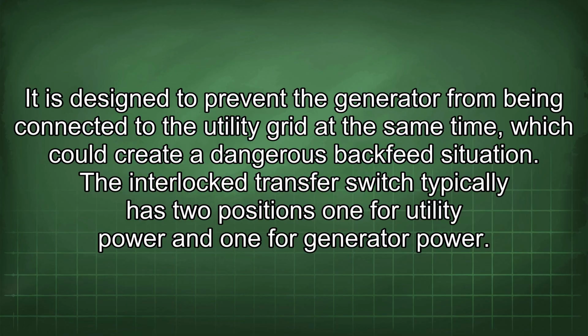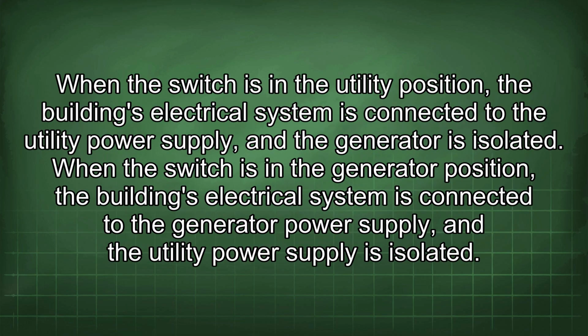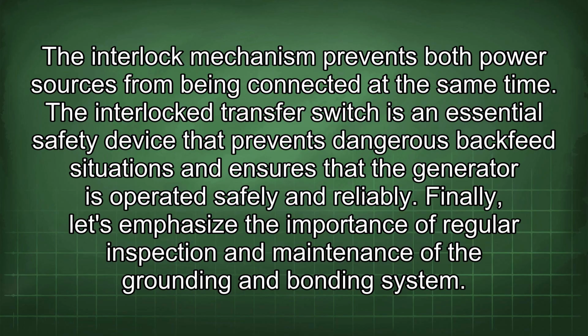The interlock transfer switch typically has two positions, one for utility power and one for generator power. When the switch is in the utility position, the building's electrical system is connected to the utility power supply, and the generator is isolated. When the switch is in the generator position, the building's electrical system is connected to the generator power supply, and the utility power supply is isolated. The interlock mechanism prevents both power sources from being connected at the same time.